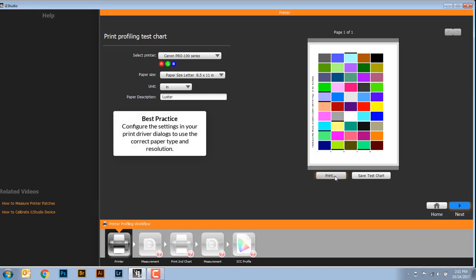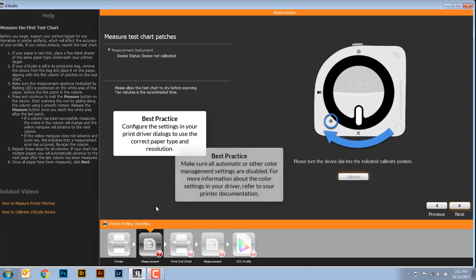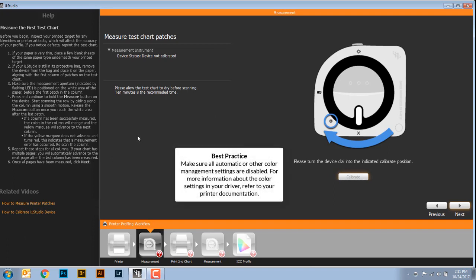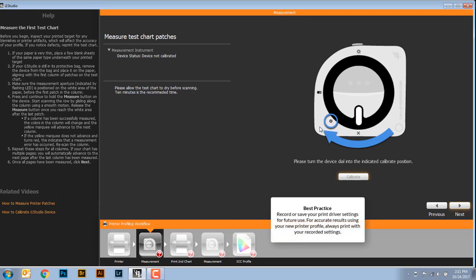Once we have our test chart printed, then we're going to go either next, or once again, we can click on the measurement tab at the bottom of the window. Before you are allowed to do any measurement, the software will indicate if the device needs to be calibrated. If it's not in the correct position, it's going to prompt you to move the rotary dial to the 7 o'clock position. Once again, this is much easier to do when you have the device outside of the zippered pouch. When you're going through a printer profile process, there's no reason for you to ever have the instrument in the pouch. It's best to get the measurements directly from the device onto the media.